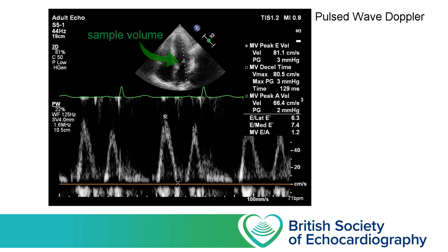Once the ultrasound machine has deduced the velocity of the moving blood and the direction it's travelling — either towards or away from the probe, based on whether the frequency has shifted to a higher or lower frequency — it needs to display that information in a way we can understand. For a single point in space it can create a graph where time is displayed across the x-axis and blood velocity along the y-axis. By convention, blood moving towards the probe is displayed above the baseline and blood moving away from the probe is displayed below the baseline. This technique is referred to as spectral Doppler.